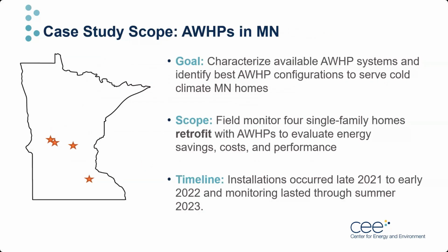So to keep things simple, single-family homes were the focus of our field study. Our goal was to characterize air-to-water heat pump systems applicable to single-family homes in Minnesota and suitable for our climate. To do this, we field monitored 4 air-to-water heat pump systems retrofit into 4 single-family homes to measure their performance. And you can see roughly where these 4 sites were on the map on the left. 3 of the 4 participating homes lie at the boundary of IECC climate zones 6 and 7, and the southernmost site is in zone 6. Our project oversaw air-to-water heat pump retrofits, which occurred from late 2021 to early 22, and we monitored these sites through this summer in 2023. Next slide.